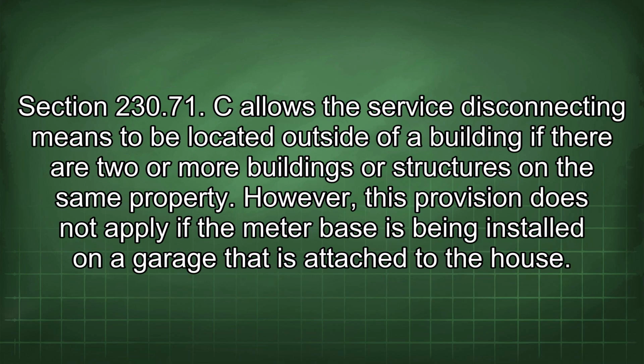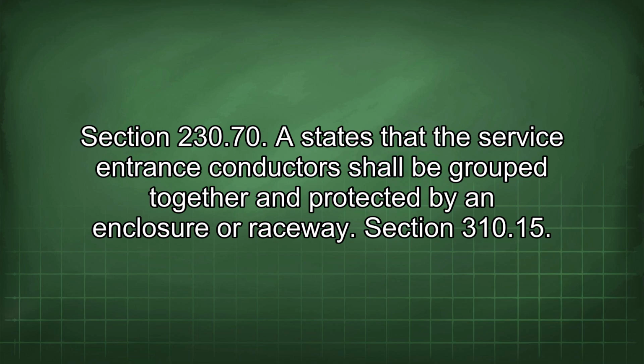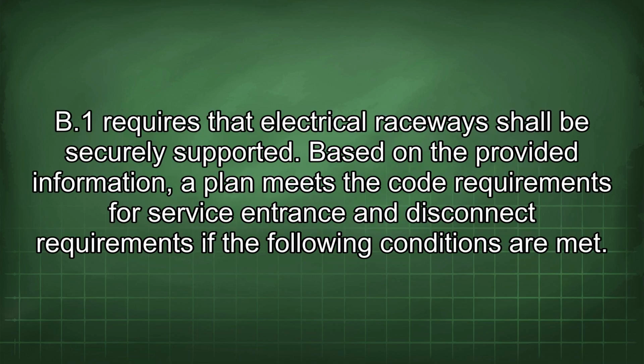Section 230.71 C allows the service disconnecting means to be located outside of a building if there are 2 or more buildings or structures on the same property. However, this provision does not apply if the meter base is being installed on a garage that is attached to the house. Section 230.70 states that the service entrance conductors shall be grouped together and protected by an enclosure or raceway. Section 310.15 B1 requires that electrical raceways shall be securely supported.